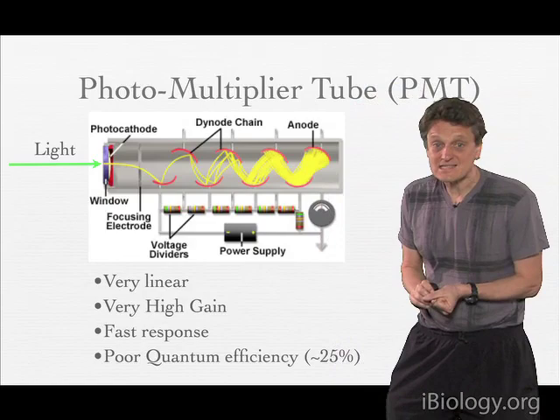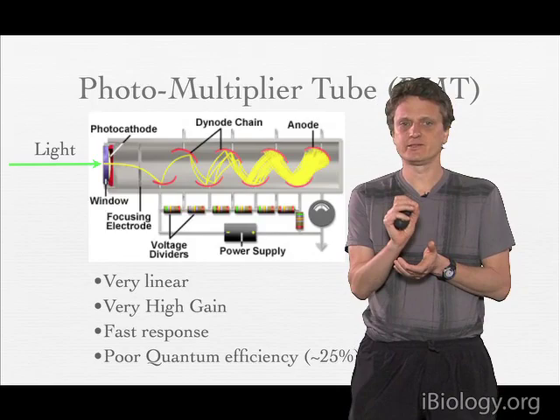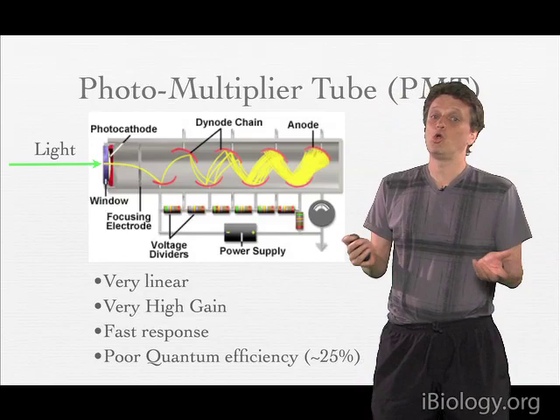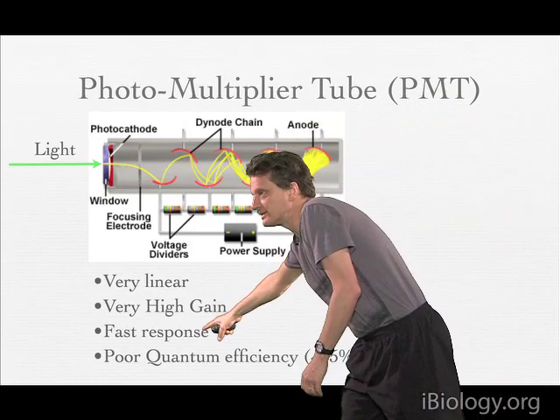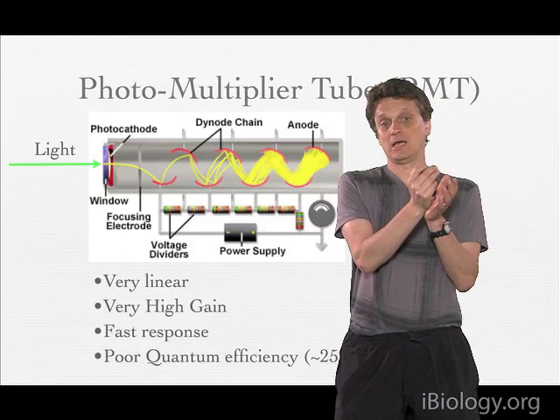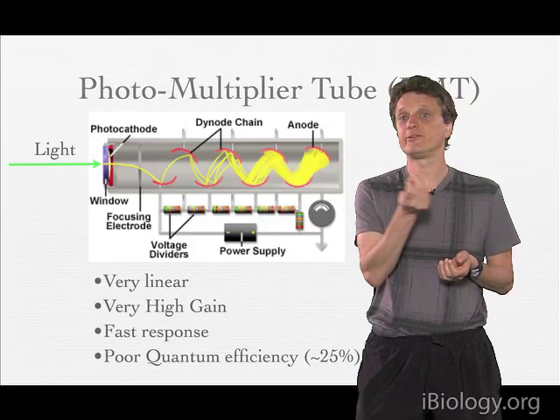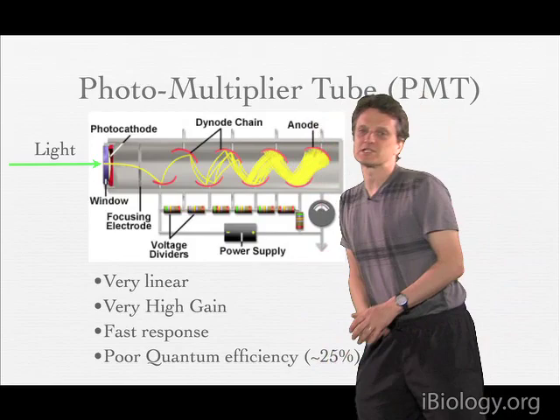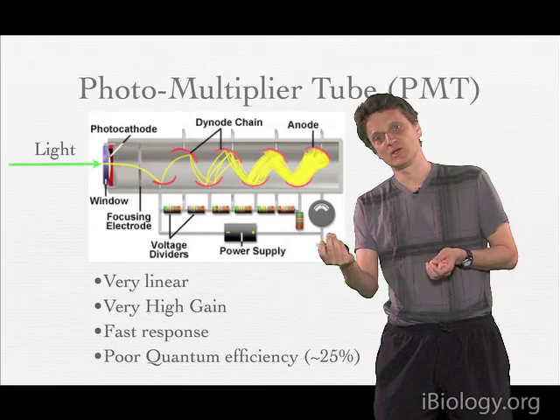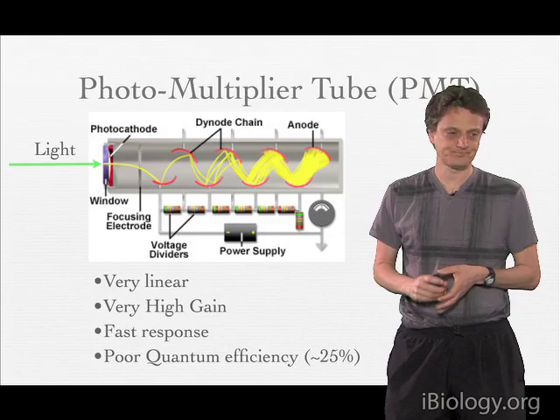PMTs are very fast, they are highly linear, and they have a very high gain so they can literally measure single electron hits. They are almost ideal measurement devices, with the main pitfall being a poor quantum efficiency. Quantum efficiency means the efficiency with which a single photon is converted into an electron. A quantum efficiency of 25% means you need on average four photons to hit the photocathode to get one electron in, and that electron you can then measure very well.